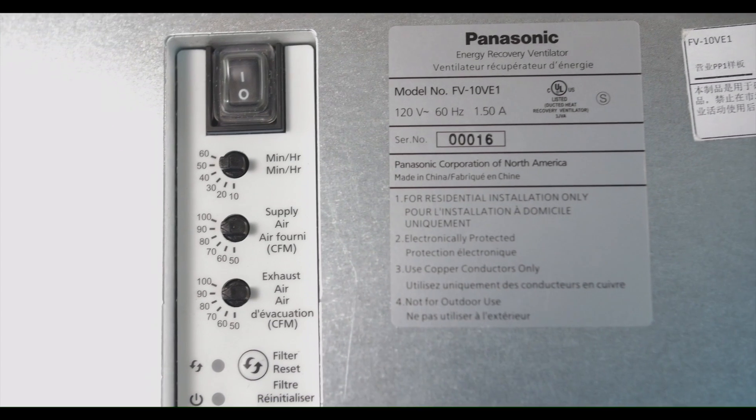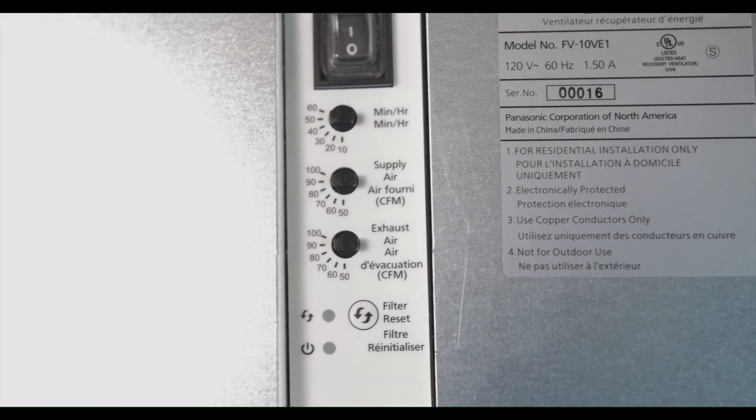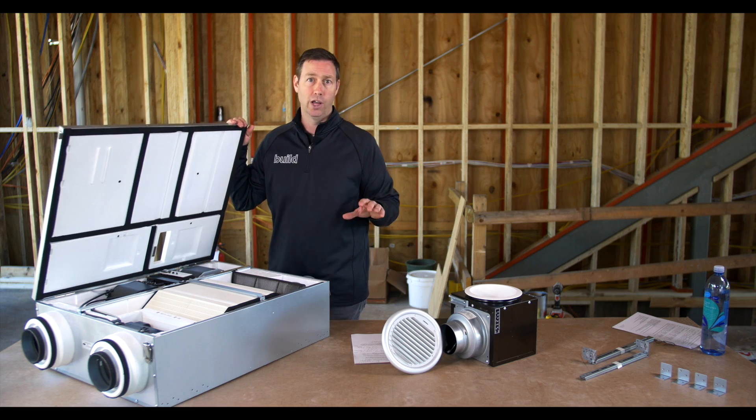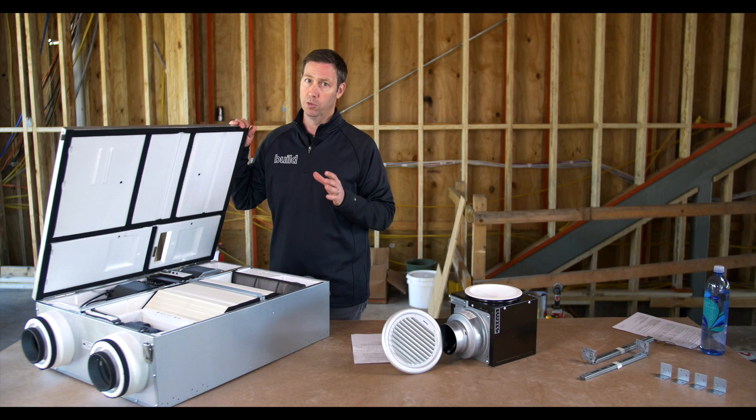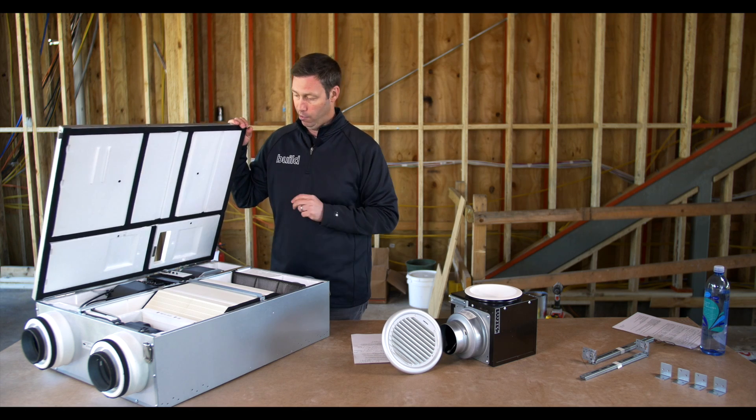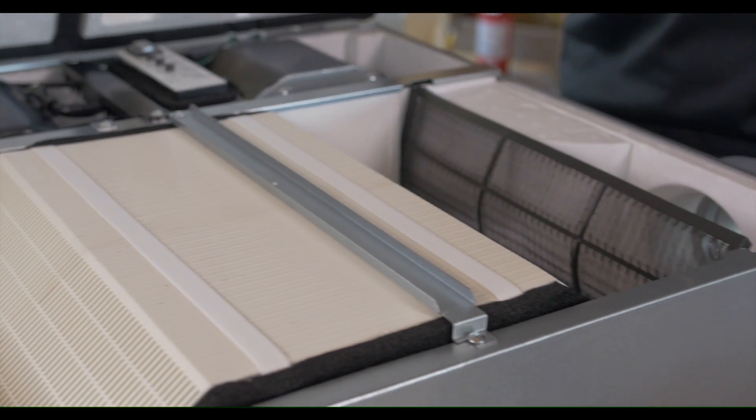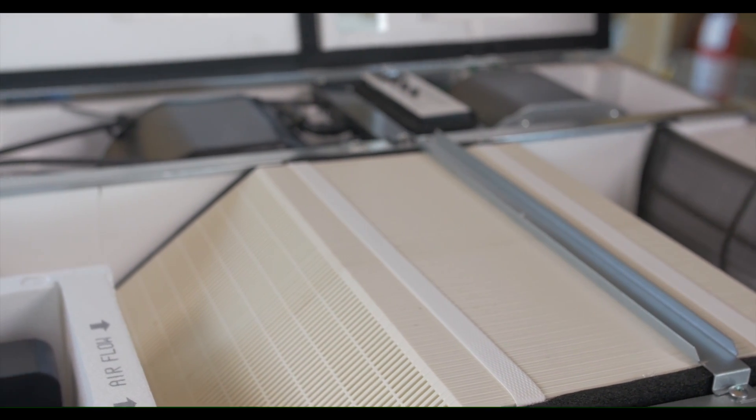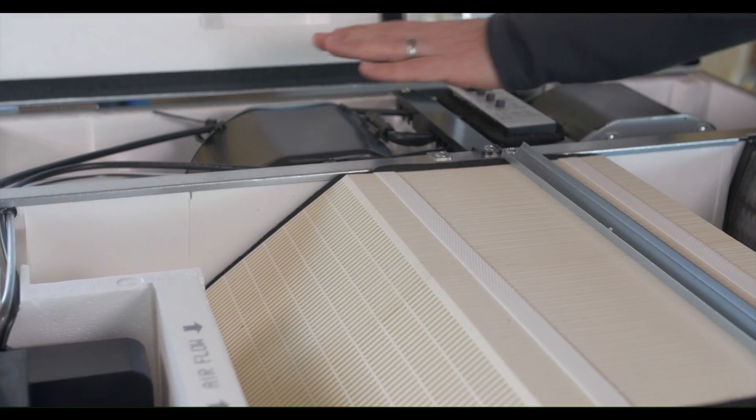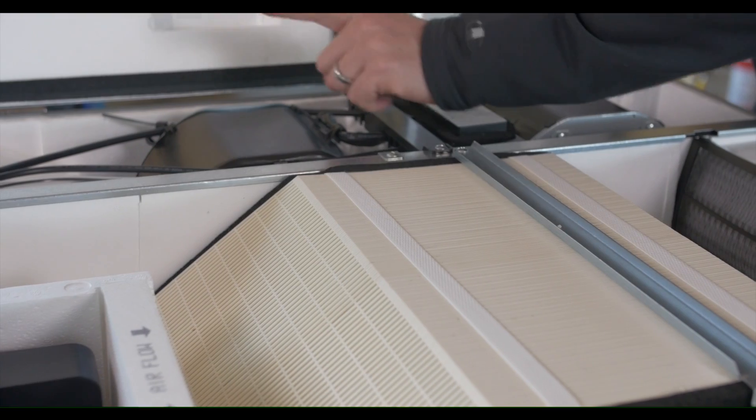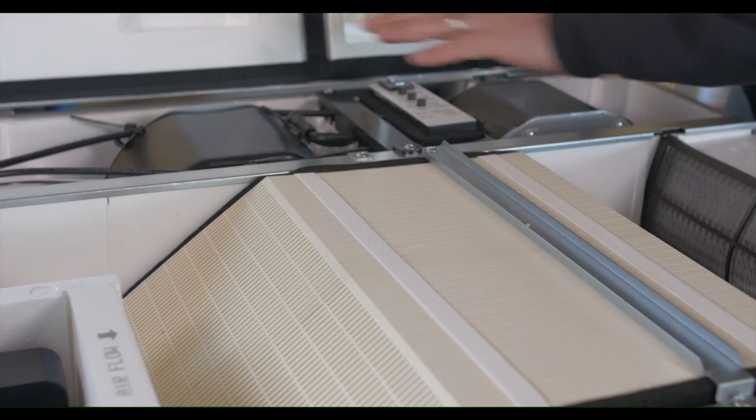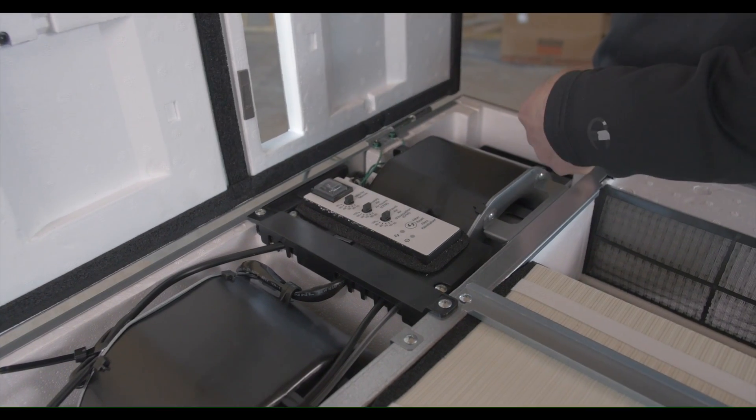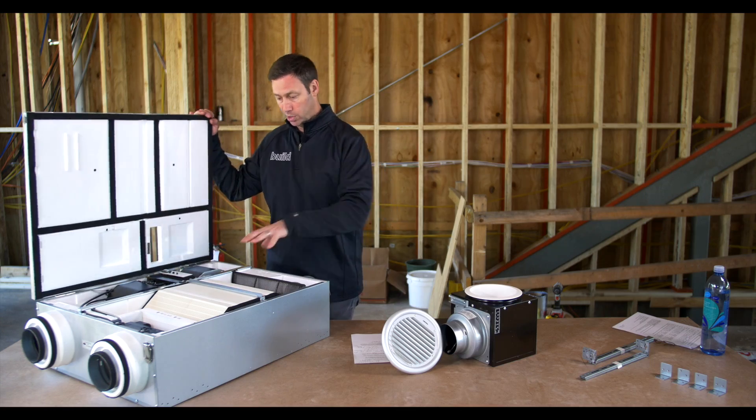With these DC motors, it also brings a lot of efficiency. When this thing is running full tilt at 100 CFM, it's only pulling down 83 watts. Very impressive. And with their SmartFlow technology, these DC motors can sense, hey I've got a restriction in my pipe. I need to actually ramp up my motor speed to get to the CFM that it says I'm delivering.